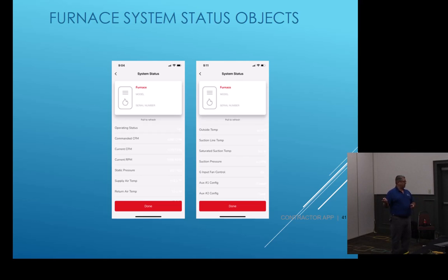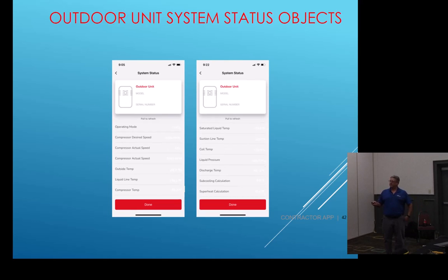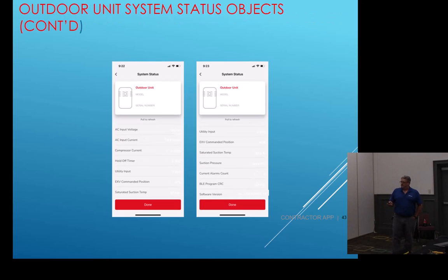So you need the app to open up the furnace. If you're having some problems with that flame sensor, it's going to tell you whether it's good, bad, weak, low, all right? So that's going to be a way you can troubleshoot because it's a digital signal, right? Outdoor unit, we can get compressor speed. If it's running off that drive, we can get compressor speed, outdoor temp, subcool, superheat, discharge temps, liquid pressures, coil temps. A lot of great information off of there, okay?